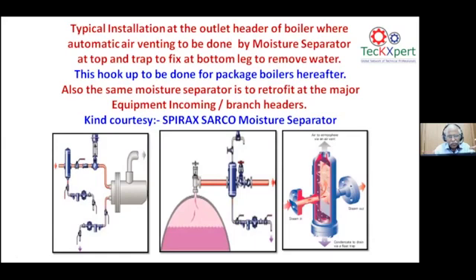Steam dryness has to be kept more than 95%. That is the dryness; the moisture percentage in steam should be less than 5%. The moisture separator is to be installed at the boiler, at the load end and at the headers, to see to it that the steam is always kept dry and does not have moisture of more than 5%.